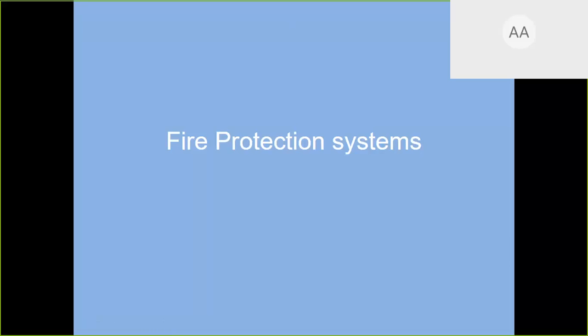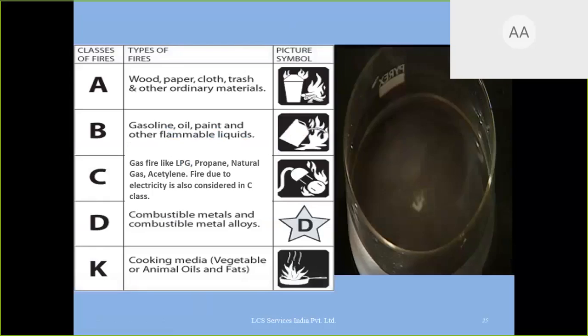So first in fire protection, the easiest, which everybody knows, is the fire extinguisher. Which fire extinguisher is to be used for which type of fire? There are 5 types of fire. A is solid: paper, wood, cloth, trash. This is a solid fire, A class fire. B is oil, paint and any liquid. Any liquid means petrol, diesel, paint, thinner, everything comes in B class. C is gas. Propane is a gas, natural gas, LPG, acetylene. So gas and electricity are also considered C class fire, because the fire extinguisher is the same for gas as well as electricity. D is combustible metal. Combustible metal is the metal alloy, flammable materials like magnesium, potassium. Those are D class fire. Molten metal, right?